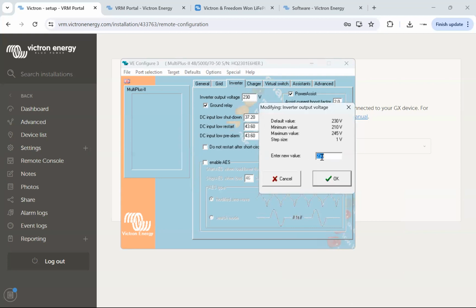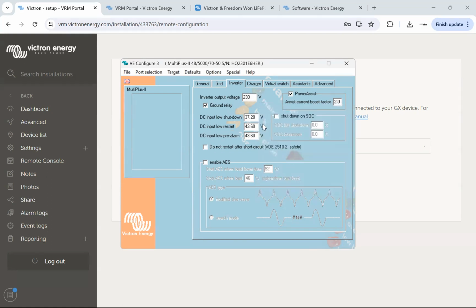AC output voltage, you can select from 230 up to 245. Normally, I just leave it at the accepted grid voltage that you're expecting or wanting. But let's say the inverter system is a long way away from the property or the house and running through an underground mains or something like that, then perhaps you could set that up a little bit to 240 volts so that by the time it gets to the house and there's a big load on, it only sags maybe 2 or 3 volts or so. So you can adjust that if you want to.